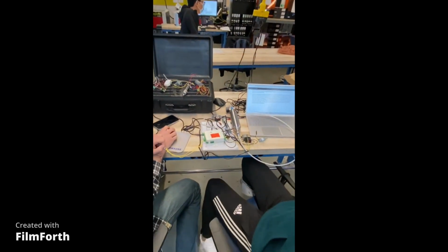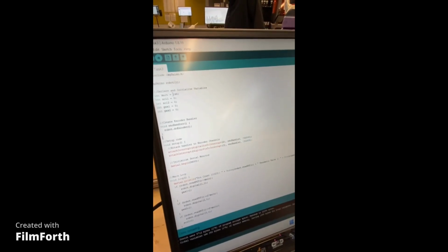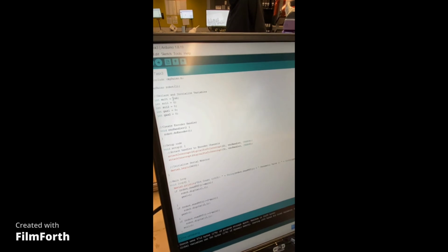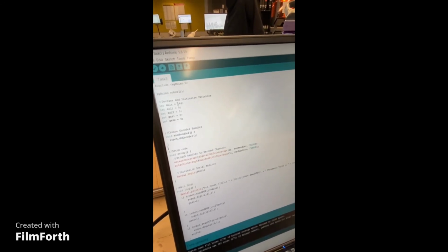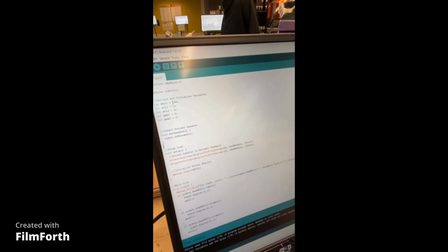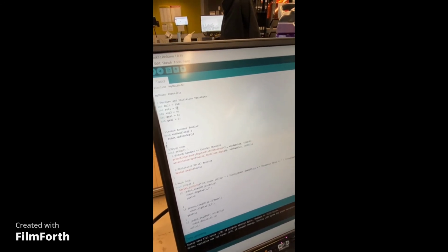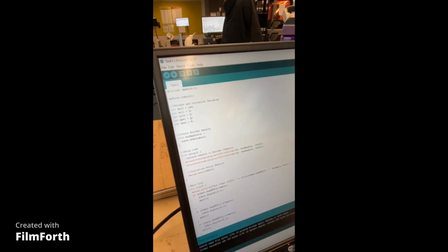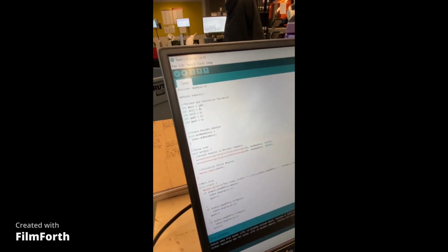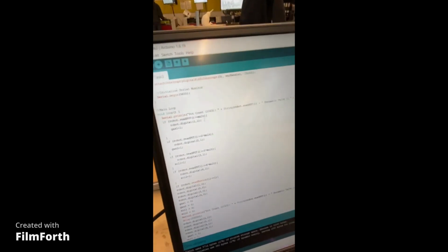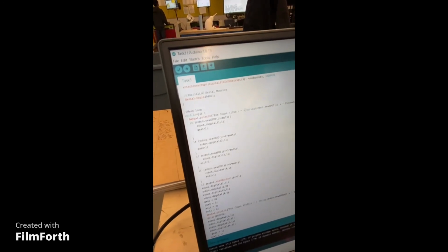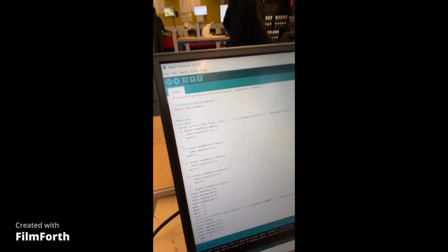Nice. Alright, up here, the multiple is the maximum number of degrees from the pot divided by 5. So the first little bit of degrees will not have anything happen until we reach a certain number. The rest of these are 0. These are indicators for the state of whether the solenoids or pneumatic valves are open or closed. We come down here. We've got this statement that's going to be printed for pot count. Pneumatic valve 1, pneumatic valve 2, solenoid 1, solenoid 2.